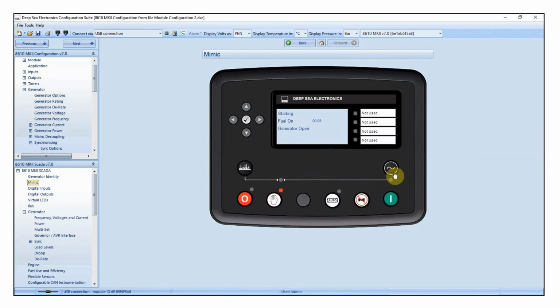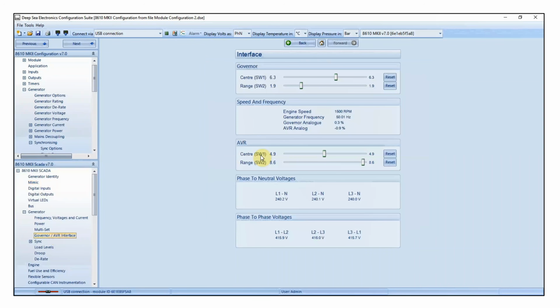So here I am starting the generator again, just waiting for that generator to become available. Again, the LED under the button will indicate when that's the case. Close the breaker. And now if we go to the governor and AVR interface section, you can see correct voltages, and also you can see that the governor and AVR analog percentages are very, very small, which is completely correct. So going back to what was asked originally, what sort of values should we expect to see for the governor and AVR analog when running our generator?